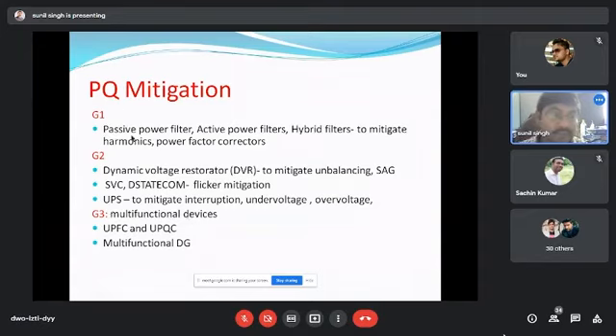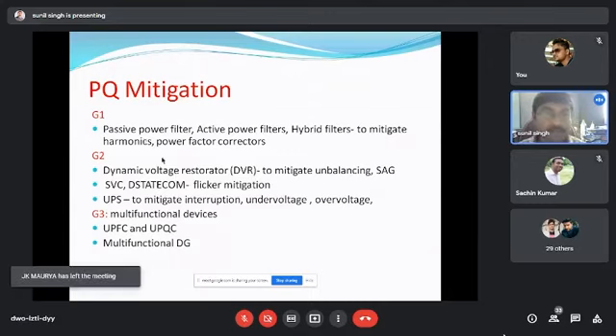So how to mitigate? First, we have generally discussed all types of power quality problems: harmonics, sags, swells, under voltage, over voltage, unbalance, all these. They can be mitigated by devices. In the first generation we are mainly concerned about harmonics. To reduce harmonics we have filters: passive power filters, then active power filters came into the picture. Then we use hybrid filters to mitigate harmonics and power factor.